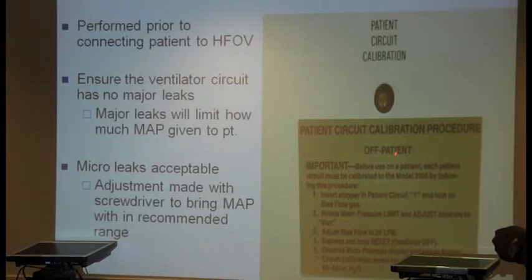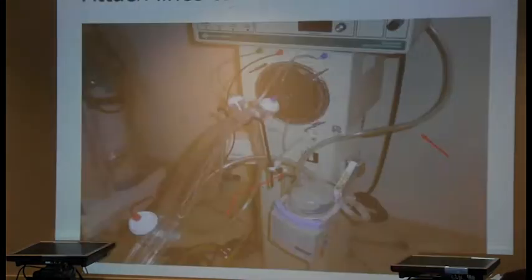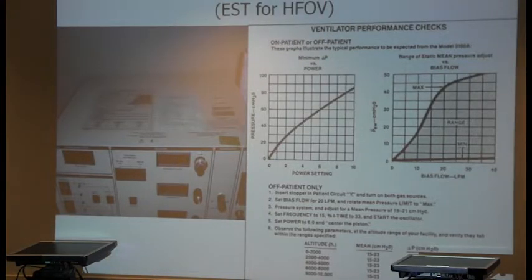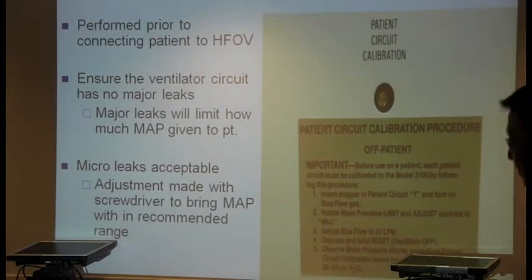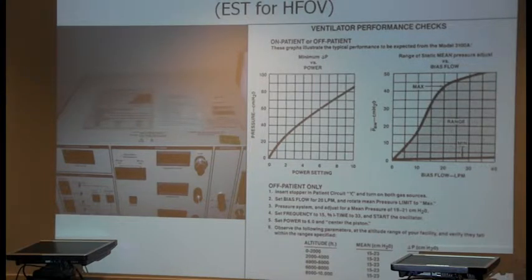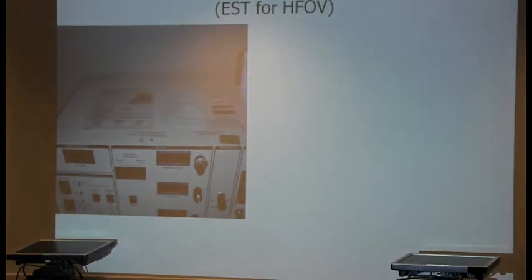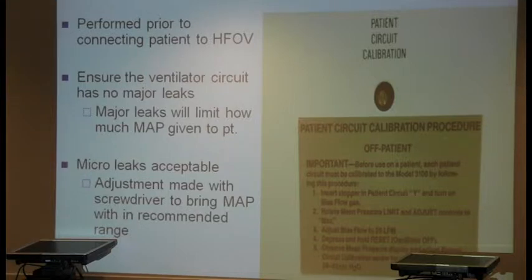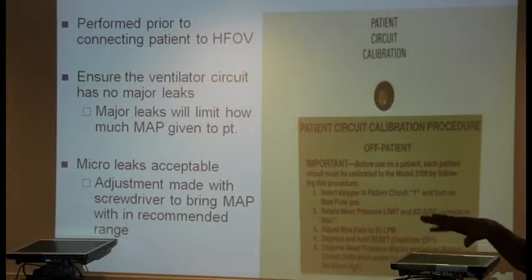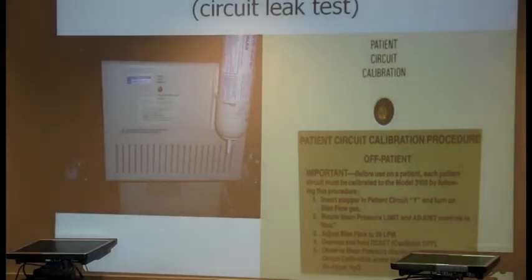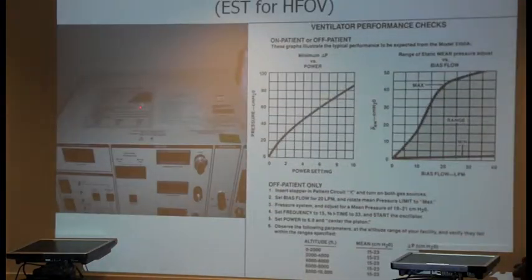But if your circuit doesn't pass, this won't pass. If this passes, I guarantee 100% of the time, this will pass. Because all you're doing is setting your values, and it's going to give you a readout of 19 to 21, and 100% of the time it comes in. But the most important piece is that you make sure this is calibrated. If you forget to do the performance check, don't worry about it. They always come in. But if you want to practice doing a performance test, I recommend you do, because like I said, it's a good way to understand how the machine operates.